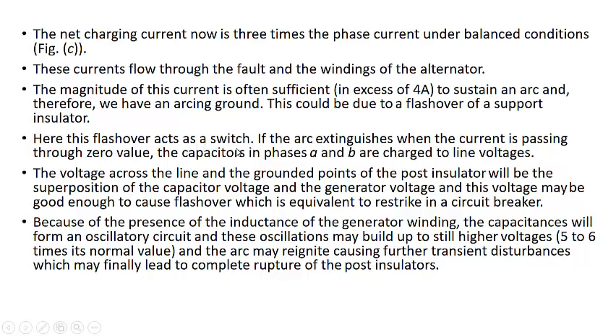Here this flashover acts as a switch. Please try to understand this line: when the arc is produced, it results in the flow of current. That AC current will pass through zero as well. When the arc current passes through zero, it extinguishes, because there will be no current and no ionization of the air. The capacitors in phases A and B are charged to line values. Now the voltage across the line and the ground points of the post insulator will be the superposition of the capacitor voltage and the generator voltage, and this voltage may be good enough to cause a flashover, which is equivalent to restrike in a circuit breaker.